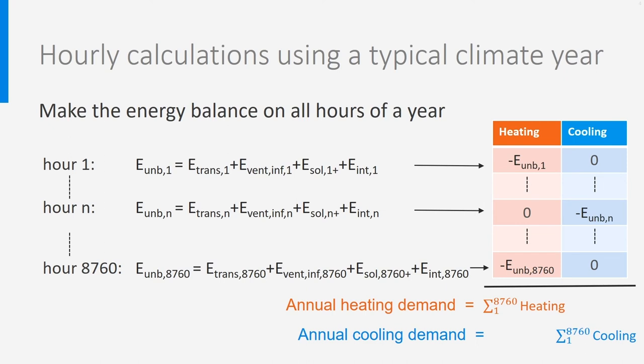By the way, this is also the principle used by most building simulation software like EnergyPlus, ESP-r, TRNSYS, etc. One additional word on the meteorological data: you can use data for one single year, but if that year was a very warm one or a very cold one, the results will not be representative of an average year. Working with the so-called TRY — test reference year — is better because it has been chosen as being representative. Even better is to use TMY years (typical meteorological year) or WYEC years (weather year for energy calculations), as they are both closer to the long-term averages.